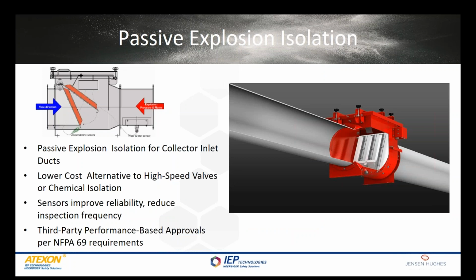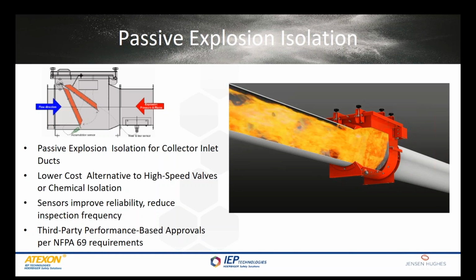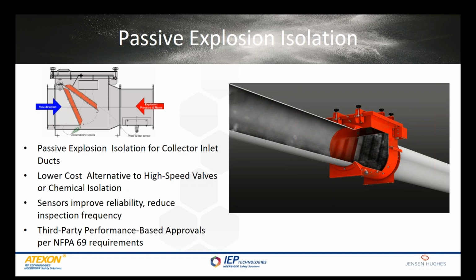Passive isolation valves typically work on the pressure from the explosion itself, causing the valve to close. So remembering the principle that you have pressure traveling much faster than the flame front, we take advantage of that principle in a passive explosion isolation valve. In this case, we're showing a flap style isolation valve where an explosion that happens from the vessel has pressure preceding it. This pressure is going to be traveling down the duct back toward the valve, and that pressure hits the flap. It causes the flap to close, creates a mechanical barrier. So basically, it's like a big check valve that's in the duct. Very simple process.